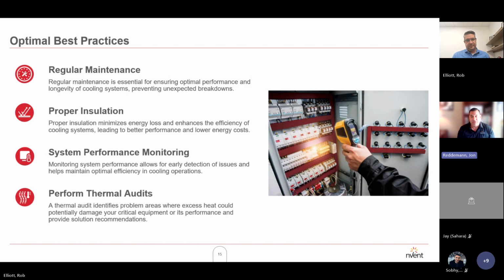Regular maintenance, just like your car, needs to have the filter changed. Fans, filters, heat exchangers, air conditioners, they're pretty maintenance free, but they do have filters that we need to change periodically. The environment is really the determining factor in how often we do that. Some environments we can do once or twice a year. Other environments we have to do monthly. I would say quarterly would be a really good time interval. Just change your filters quarterly, and that really will impact overall uptime and performance of whatever system you have.